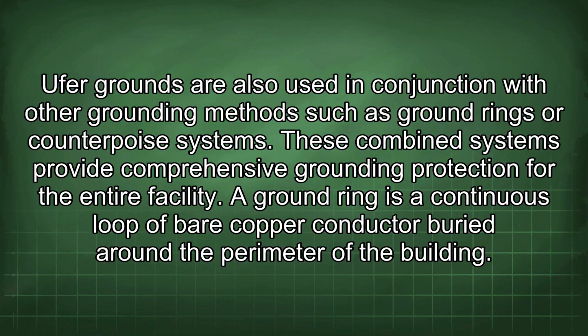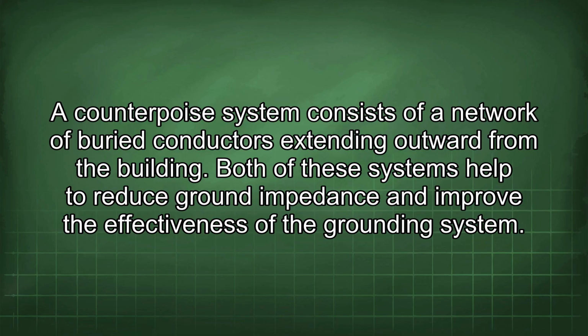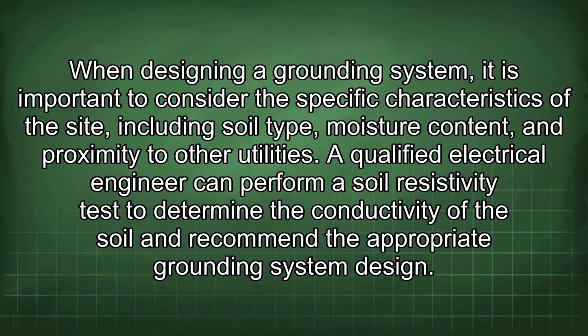A ground ring is a continuous loop of bare copper conductor buried around the perimeter of the building. A counterpoise system consists of a network of buried conductors extending outward from the building. Both of these systems help to reduce ground impedance and improve the effectiveness of the grounding system. When designing a grounding system, it is important to consider the specific characteristics of the site, including soil type, moisture content, and proximity to other utilities.